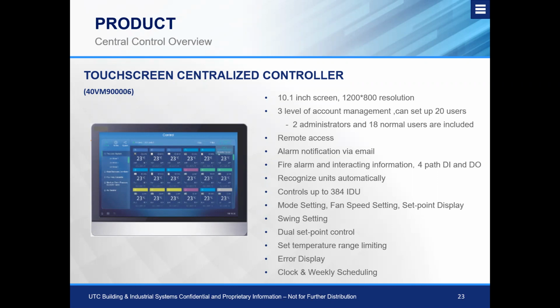And then, of course, we offer mode settings, fan speed settings, set point display, dual set point control, set temperature range limiting, with air flow display and port ventilation. We can set up clock and weekly scheduling. So this is certainly, on larger jobs, almost a crucial piece, I would say, to be able to monitor, control, and ensure that the system runs at its efficiency at all times. And if it's not, to be able to have something that we can generate error codes and system reports, integrate with other building controls and local codes, so we can access it from a centralized or a remote location.